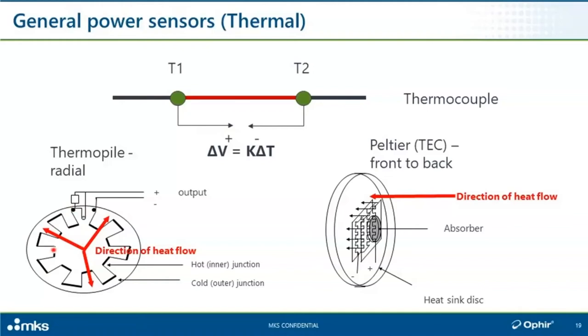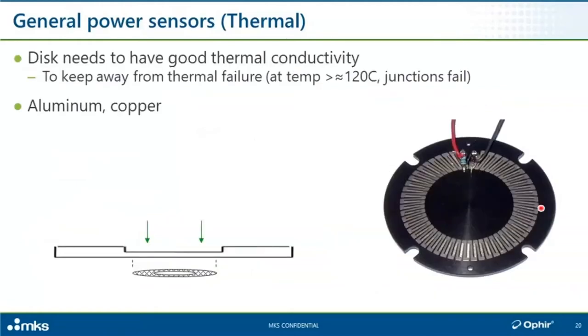One configuration is the radial configuration; all of this is hidden behind the front mechanical flange of the sensor body — only the active aperture is visible. The other configuration is an axial configuration where the heat flows front to back — these are more sensitive sensors, going down to maybe 10 microwatts. It's more sensitive but a little bit slower. Everything has its pluses and its minuses.